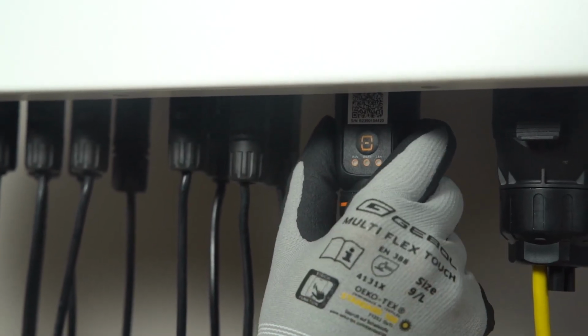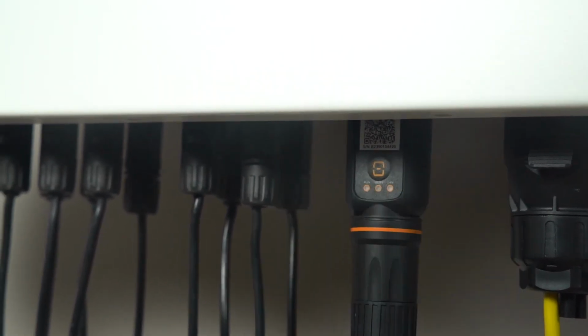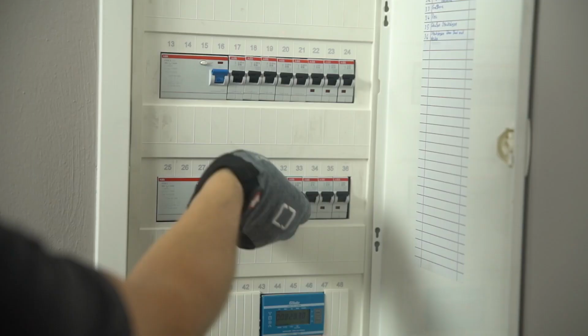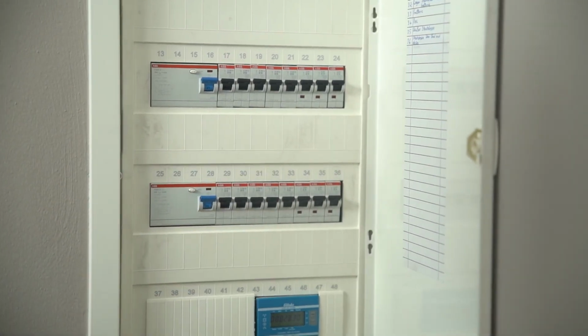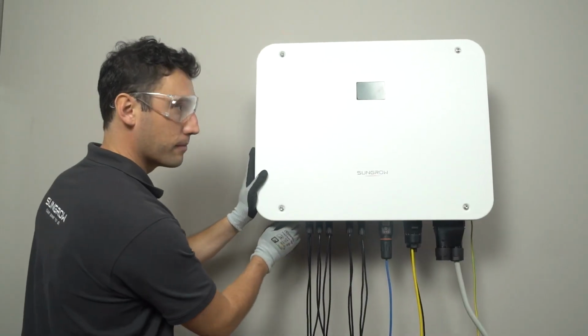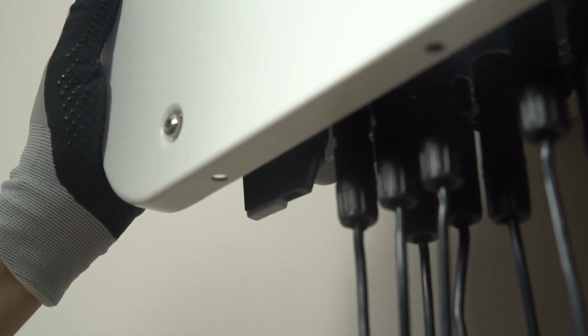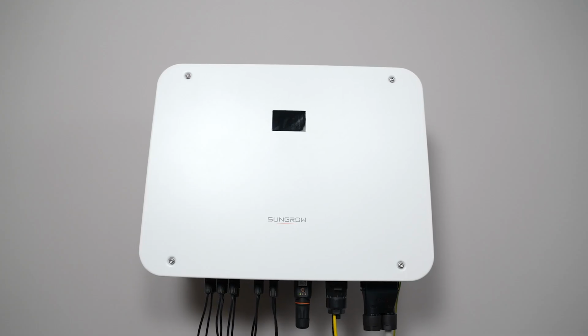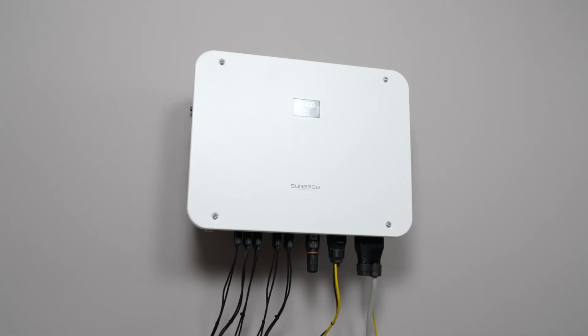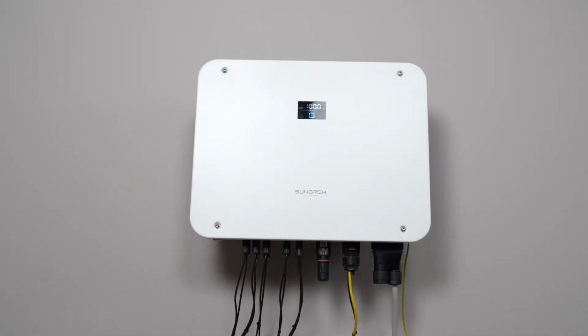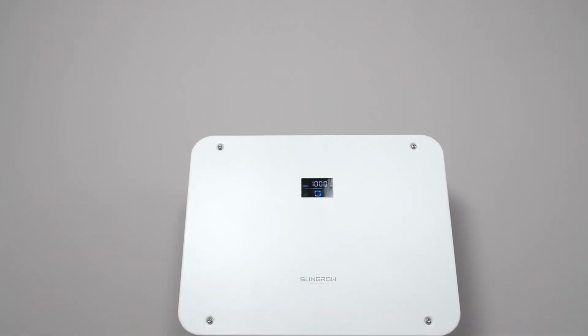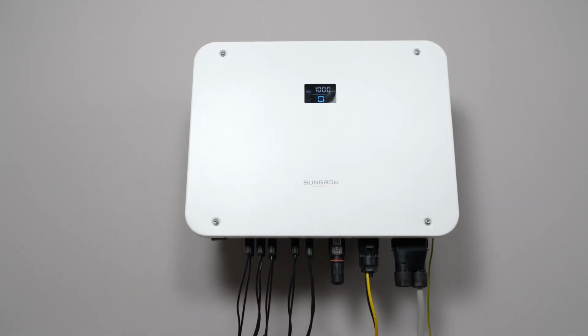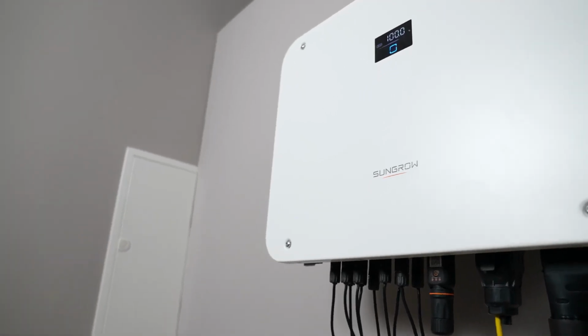The installation is done. Now it's time to turn on the power. First, you have to switch on the AC circuit breaker. Next, set the DC switch on the left side of the inverter to the on position to connect the inverter to the PV generator. Now the LED display will turn on. You can touch the LED indicator to see all information. To receive comprehensive commissioning instructions, check out our commissioning videos.